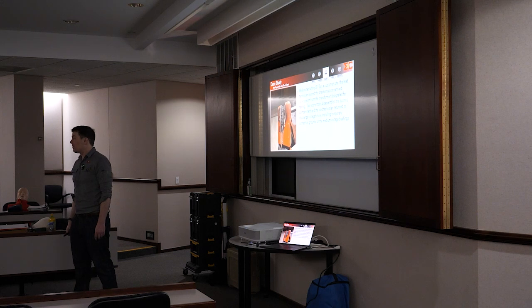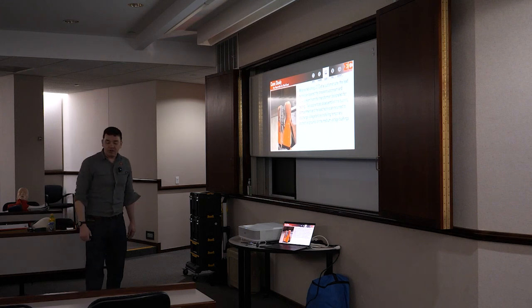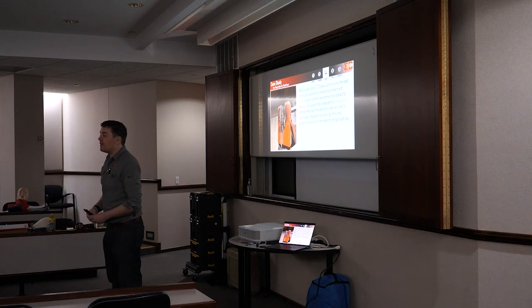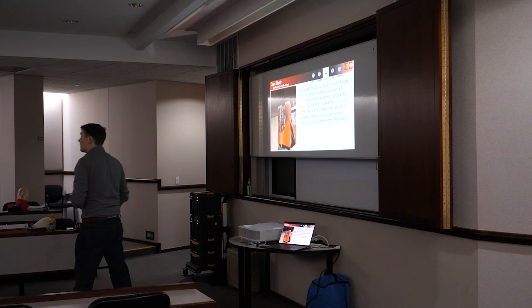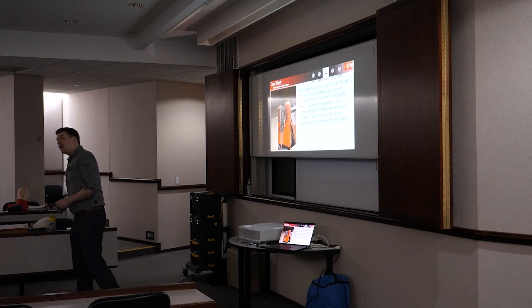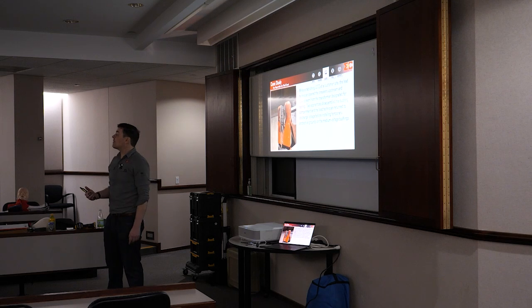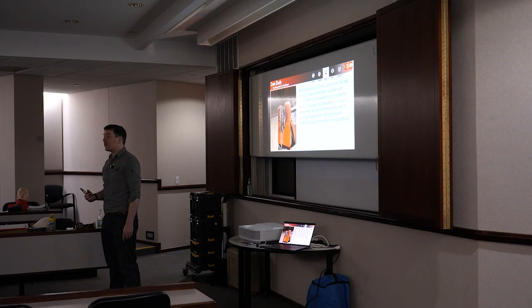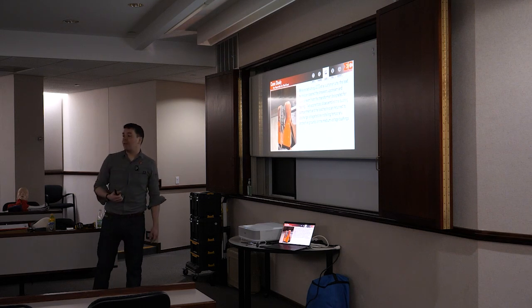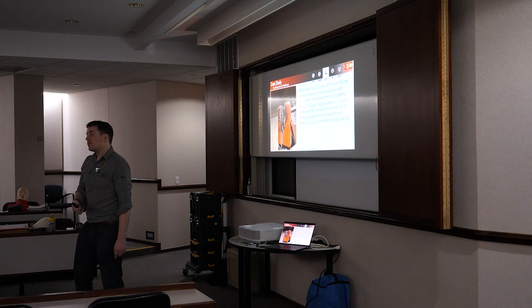So whenever possible, take those verifications, ensure that you are indeed working on something that is totally de-energized, especially when dealing with something like 15 kV. Your 480 volt systems generally have higher amounts of available fault current, but your 15 kV systems are the ones that can jump across air and destroy you without you even knowing what happened. You can verify that.